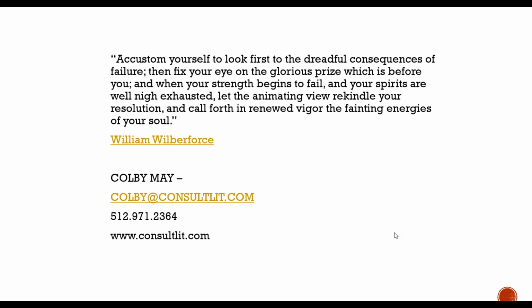Just had a client, Academy, just did plug and plays on all 200 stores, and they replaced all 32-watt T8 bulbs with 14-watt LED equivalents, and they didn't even change the fixture. They just took the ballast, took the bulb out, and put an LED bulb in. Wow. There are cost-effective ways to do that. And you can go buy an LED bulb for $5 to $10 at Home Depot, something to consider.